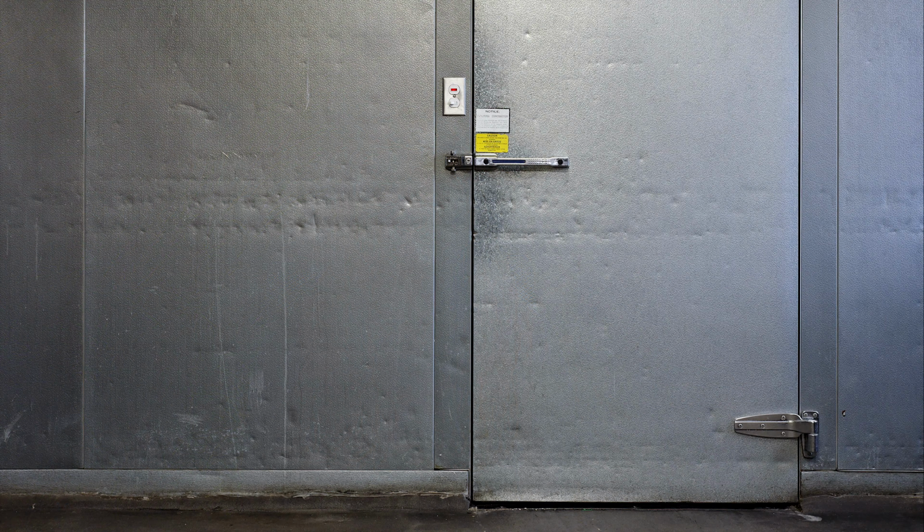Much like refrigerators, hardware upgrades can bring huge improvements to the energy efficiency of chiller and freezer rooms. Any improvements to the insulation of the walls, roof and ceiling will help reduce the energy demand. Door upgrades, such as insulated strip curtains or rapid close doors, both reduce the heat gain to the cold storage space. Fan and door interlocks can also be installed, turning off the fans when the doors are open. This stops the cooled air from being expelled from the room. Check that your automatic defrost system is not set to defrost too often.